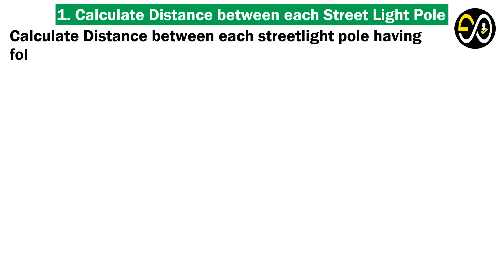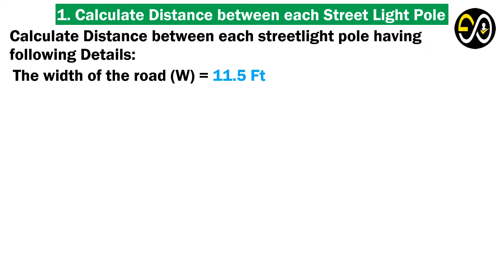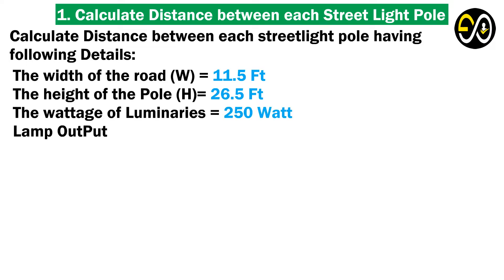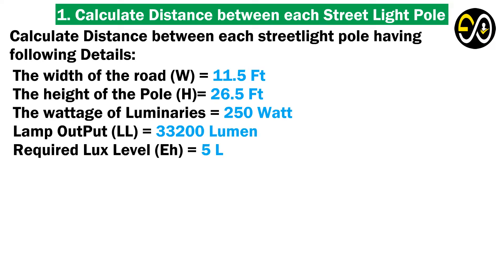Example 1: Calculate the distance between each street light pole given the following details. The width of the road W equals 11.5 feet. The height of the pole H equals 26.5 feet. The wattage of luminaires equals 250 watts. Lamp output LL equals 33,200 lumens. Required lux level equals 5 lux.